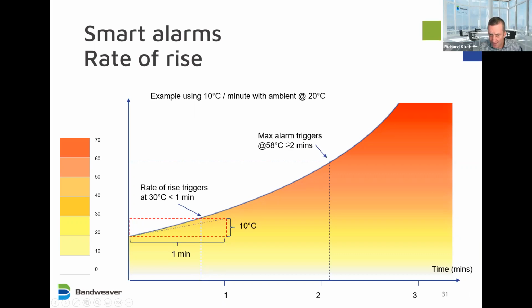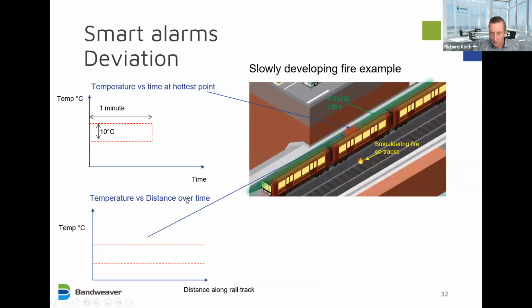If we were waiting for the maximum alarm set at 58 degrees C, which I mentioned is the normal, you'd be waiting more than 2 minutes. And this is a good backstop to have in. There's still a place for this, but typically rate of rise is one of the smart alarms that triggers earlier. The other alarm we mentioned was deviation, and deviation can be very effective when you have a slow fire.